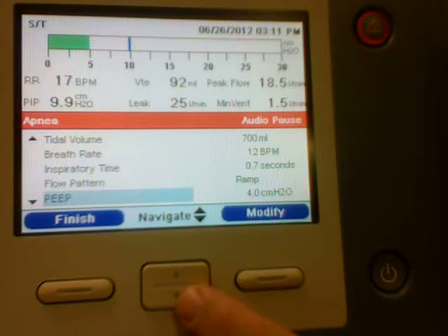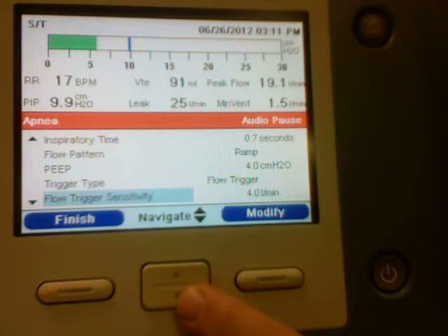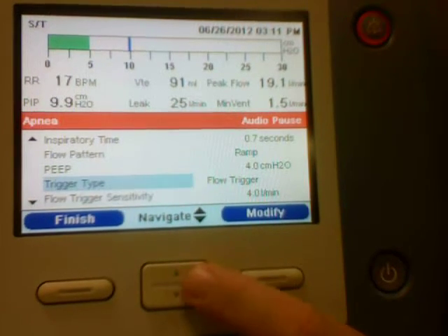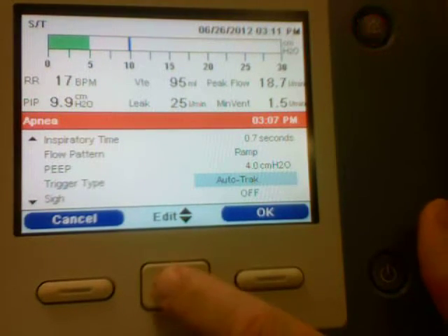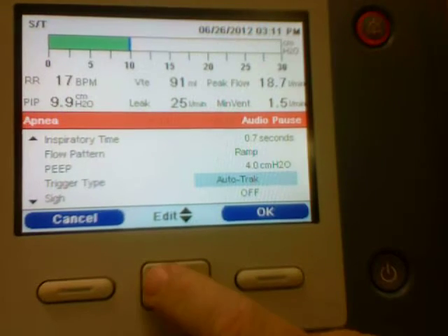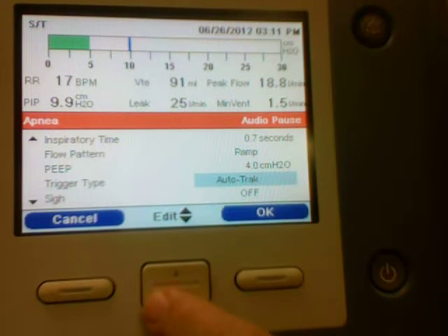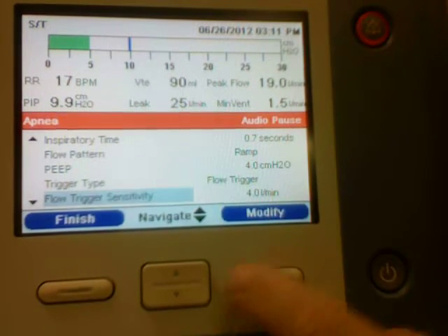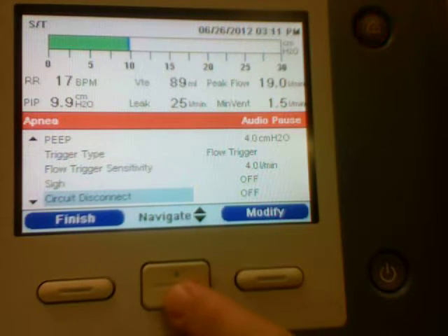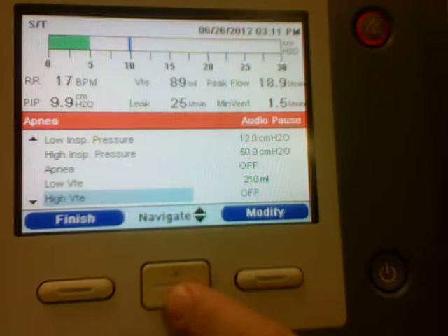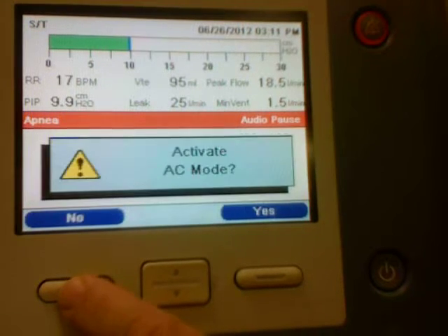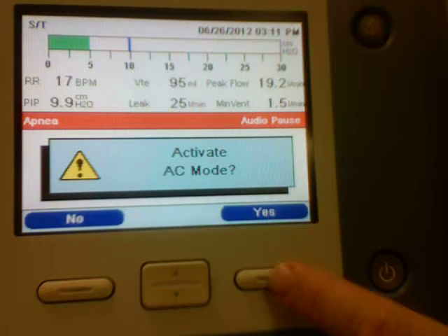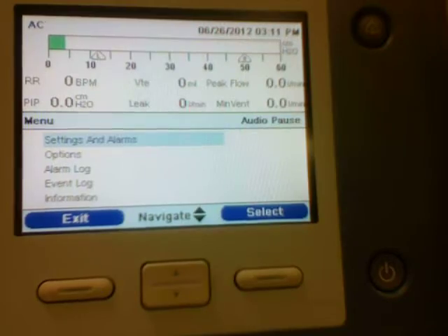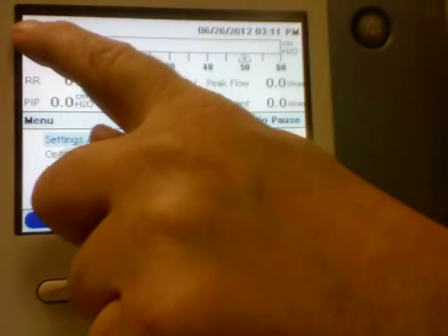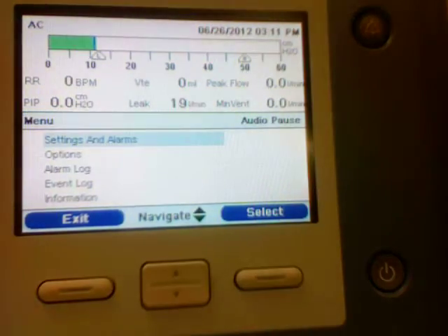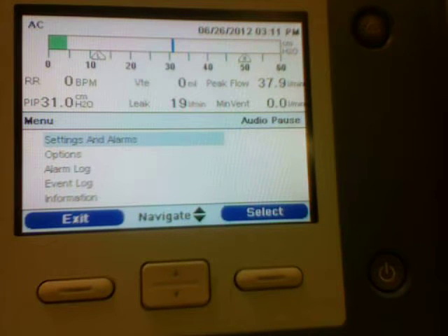PEEP, again, I can set my PEEP. Now I'm in a flow trigger. Let's see what my choices are here. Again, I can use the Auto-Trak, or I can use a flow trigger and set that. Alright, circuit disconnect, and all my alarms, and so on. Activate assist control mode. Hit this button, yes. Okay, now you can see here I'm in assist control mode, rate of 12, 60 liters a minute.